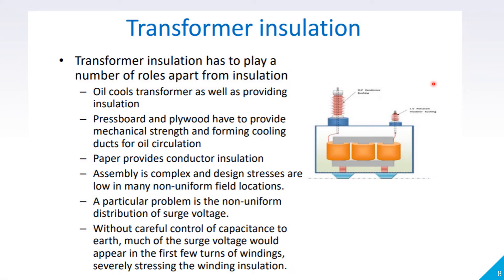Let's take the first example: transformer insulation. Transformer insulation has to play a number of roles apart from insulation. Mineral oil is used as both insulation and coolant — it cools the transformer as well as providing insulation. Pressboard and plywood provide mechanical strength and form cooling ducts for oil circulation. Paper provides conductor insulation. The transformer winding and core assembly with all insulation layers is immersed in transformer oil, which acts as coolant and insulator. Bushings serve as insulators.